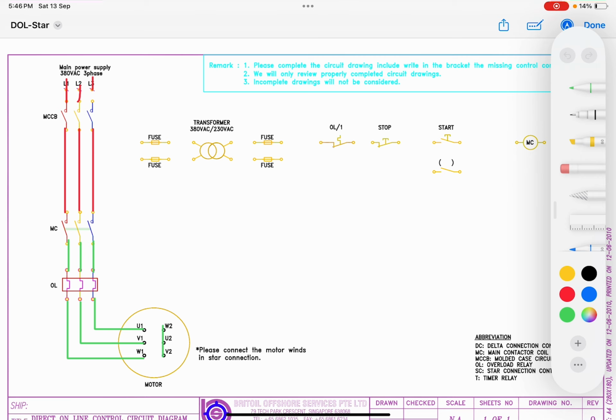Now we can see that the power circuit is completed. Once your power circuit is done, we are going to connect it to the control circuit. First of all, from the main line we have to take 2 lines to the fuse. From here, this 440 goes to your fuse, and after the fuse it is going to go to your control transformer. This control transformer is stepping down the voltage from 440 to 220. After the fuse and transformer, this is the primary side of the transformer and this is the secondary side. At the secondary side of the transformer we have 230 volt AC.